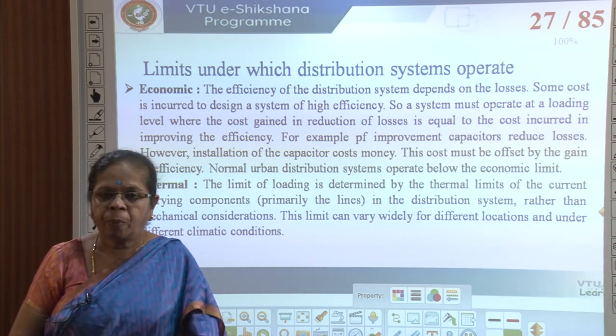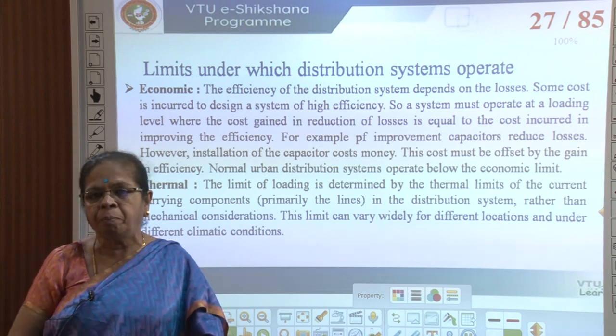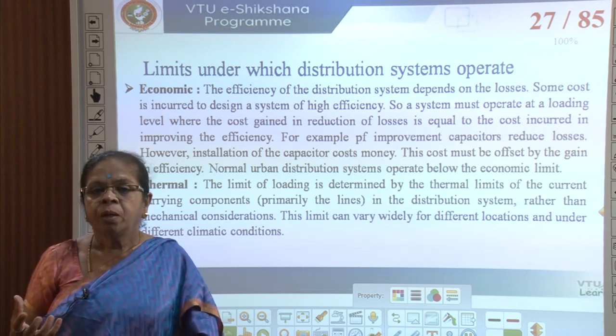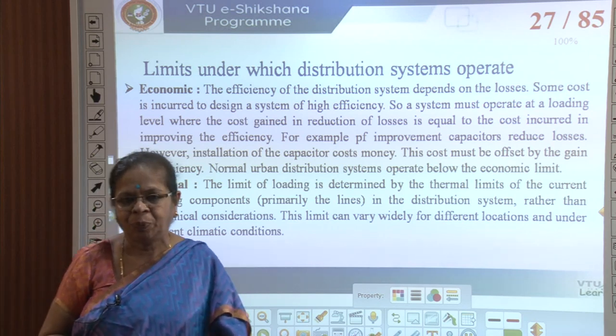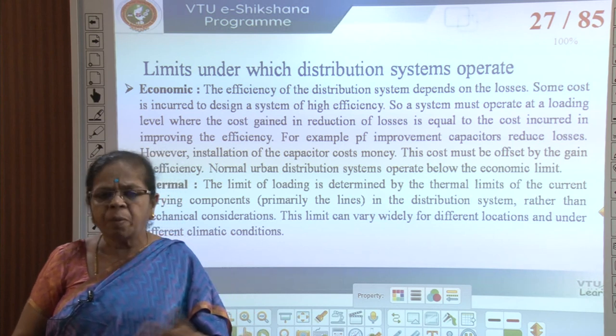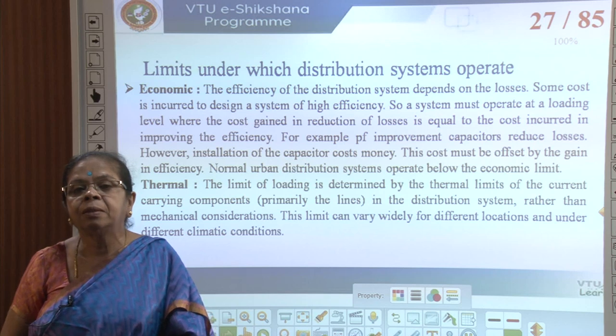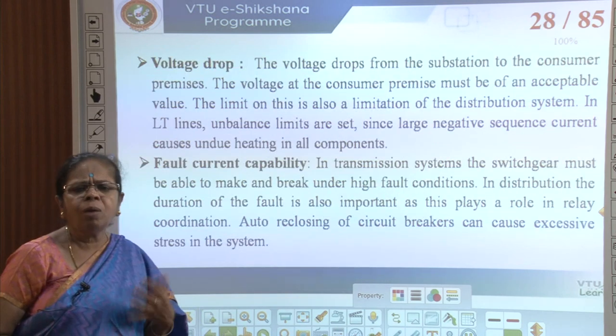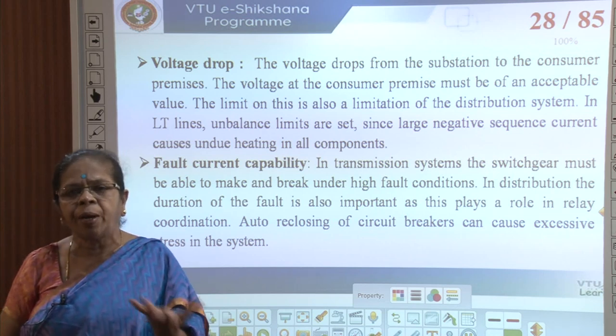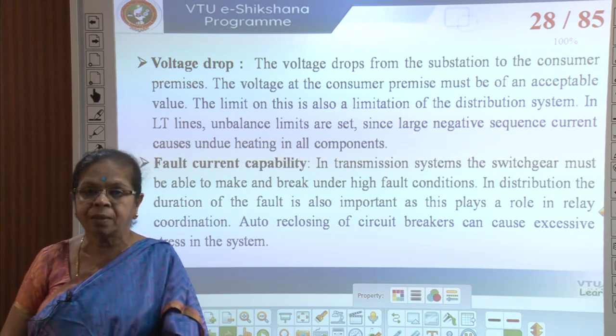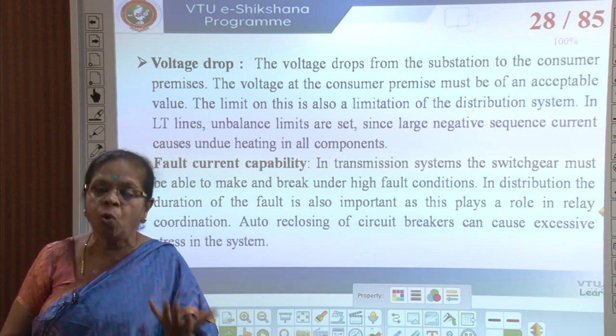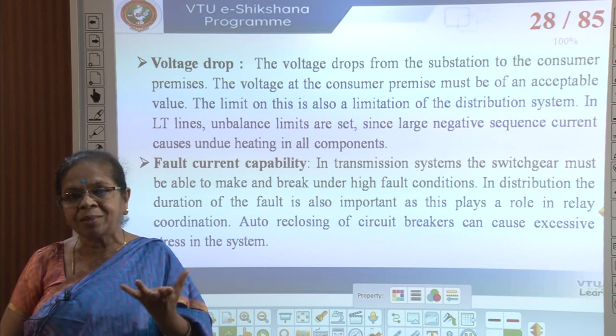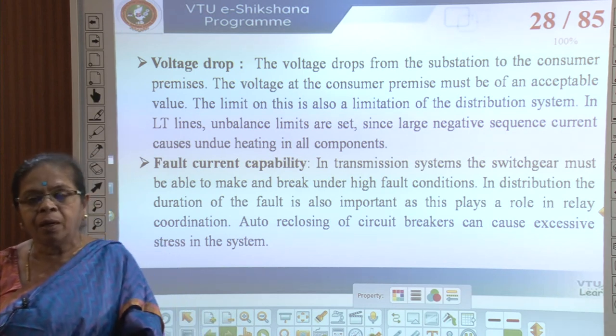Then we have thermal loading — the limit of line loading based on thermal limits — meaning what is the maximum power a distribution line can carry before it gets heated up enough to melt. This depends on the type of conductor, the geographical location, and the ambient temperature. Lines are operated well below the thermal limit for various reasons. The lines must be capable of carrying much more load than normal in case of faults, so we need lines of higher capacity carrying lesser load under normal conditions.